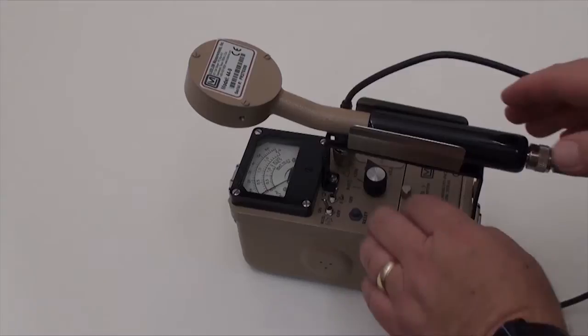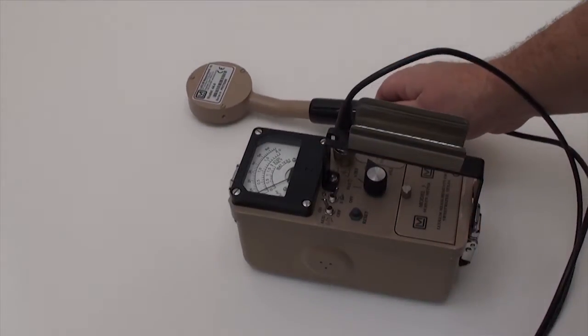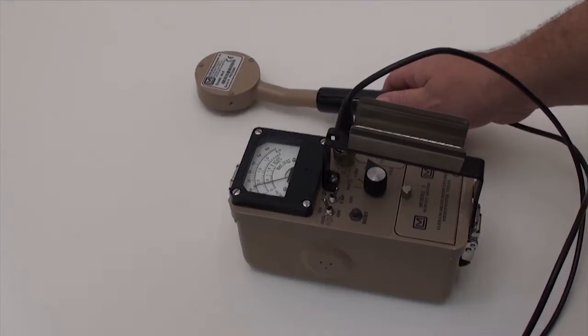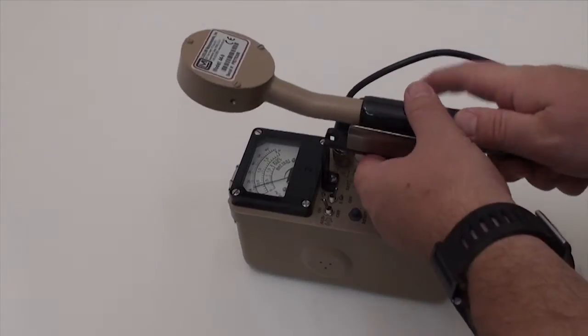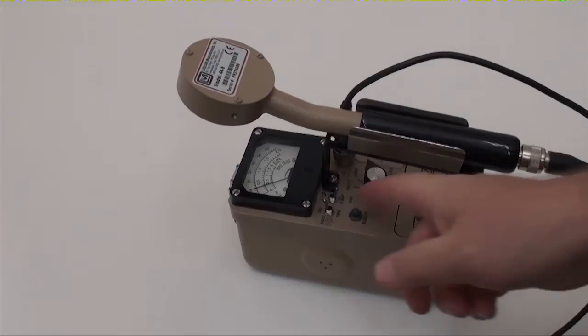The Model 3 supports almost any pulsed output detector with an operating voltage between 400 to 1500 volts. Here we see Ludlum's very popular model 44-9 GM pancake probe attached.